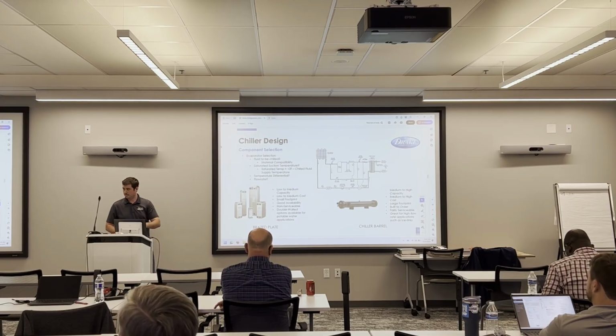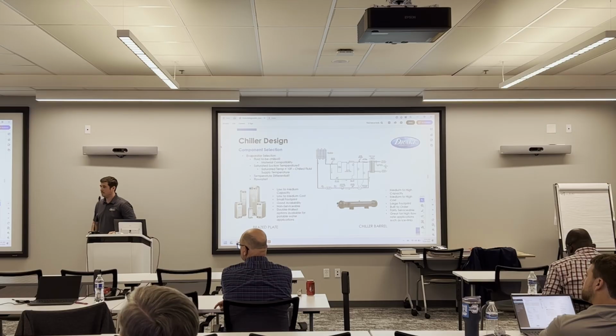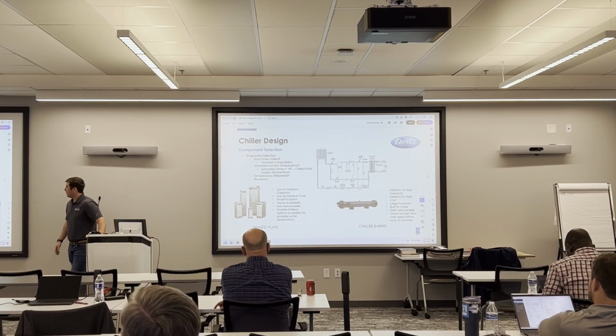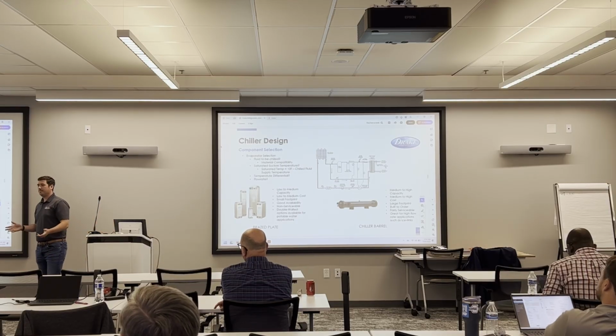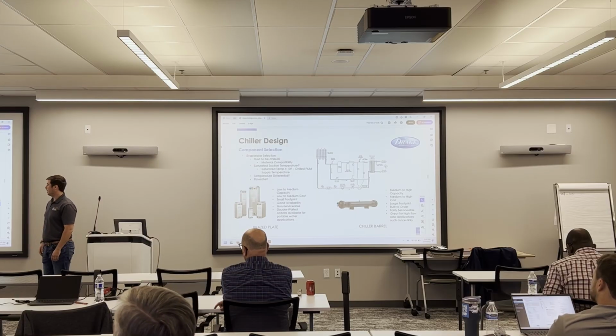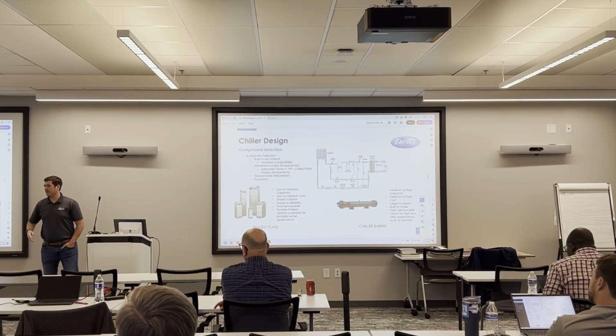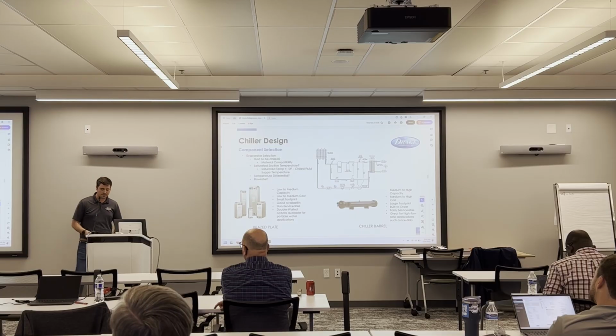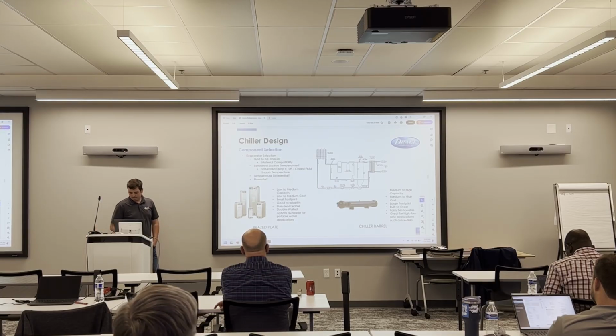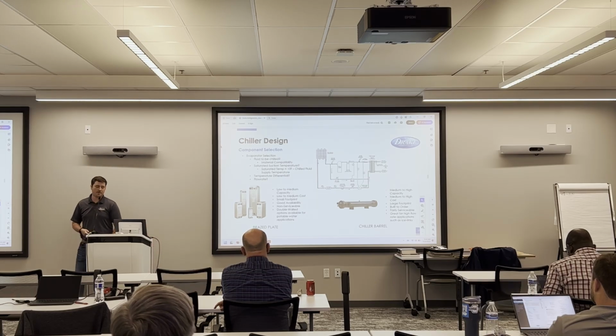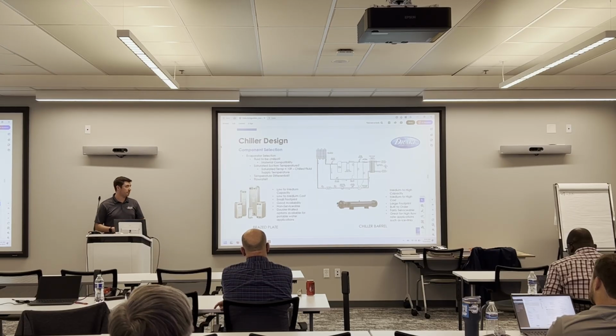As far as the capacity, can you say what you mean by low to medium or medium to high? Which capacity is it? I'll say low to me is like a quarter ton, so we'll say 2,500 BTUs up to 500,000 BTUs would be your medium, and then anything above that I would consider high capacity. So 500,000 to 2 million BTUs would be high capacity. And then just another thing with these brazed plates, they're not really good at high flow rates, so if you're going to have a massive flow rate like 500 GPMs and above, it's probably best to go with the chiller barrel, or you're going to have a massive pressure drop across that brazed plate heat exchanger.